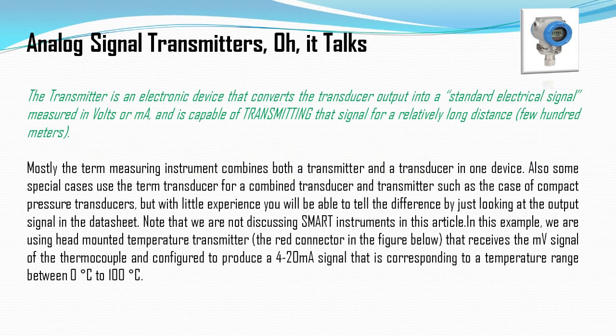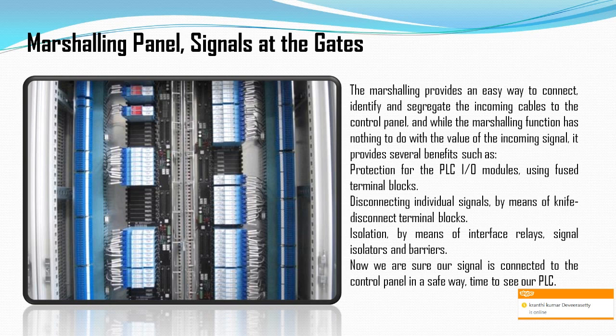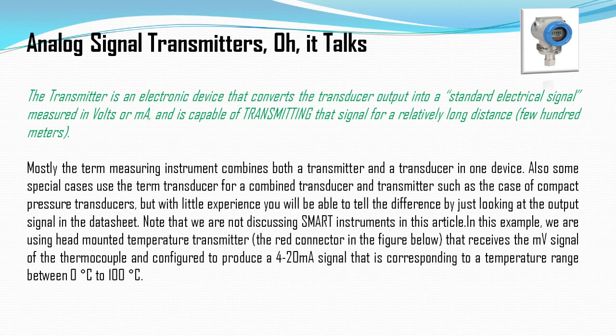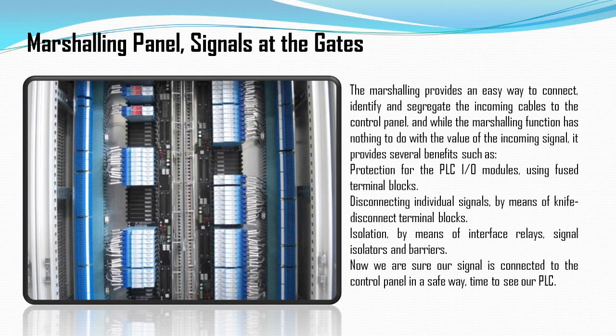To communicate with the field or any process, we need a transmitter. When signals come from the field, we also need a marshalling panel. The signals coming from transmitters are normally in 4 to 20 milliamperes or 0 to 10 volts — these are standard signals. When they reach the terminal board, fuse protection is needed before passing signals to the input module of the PLC or DCS.